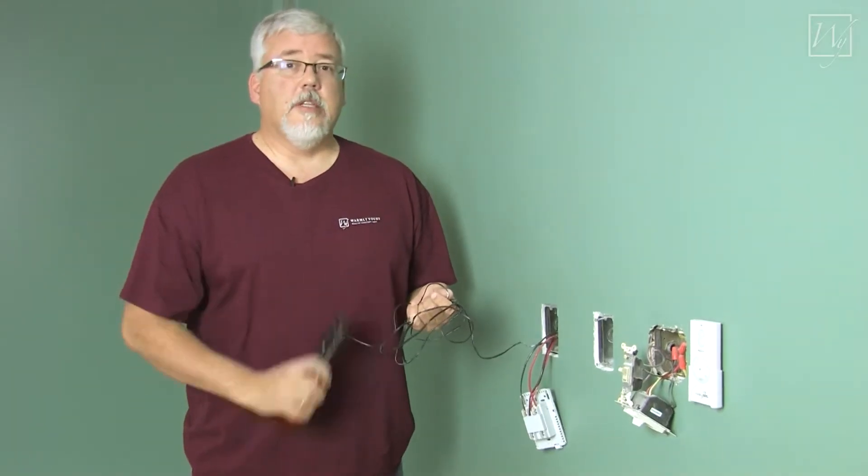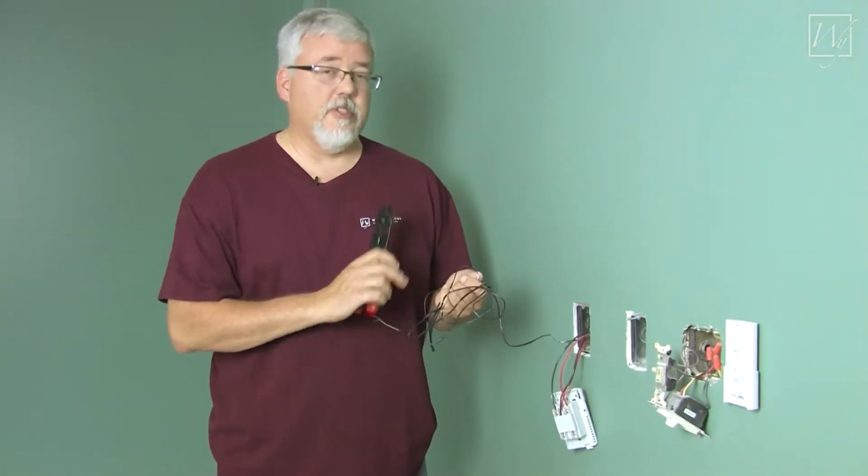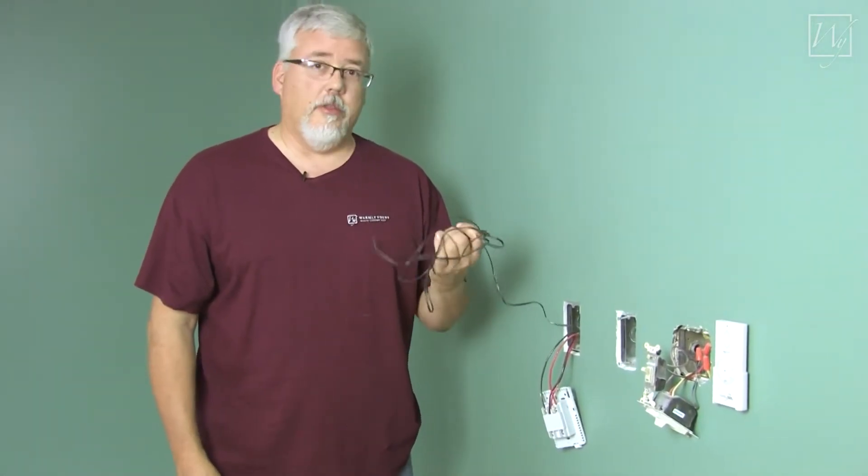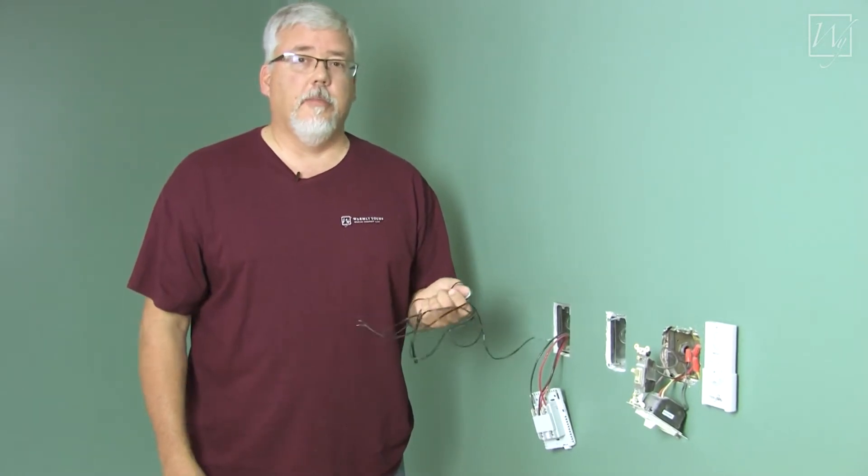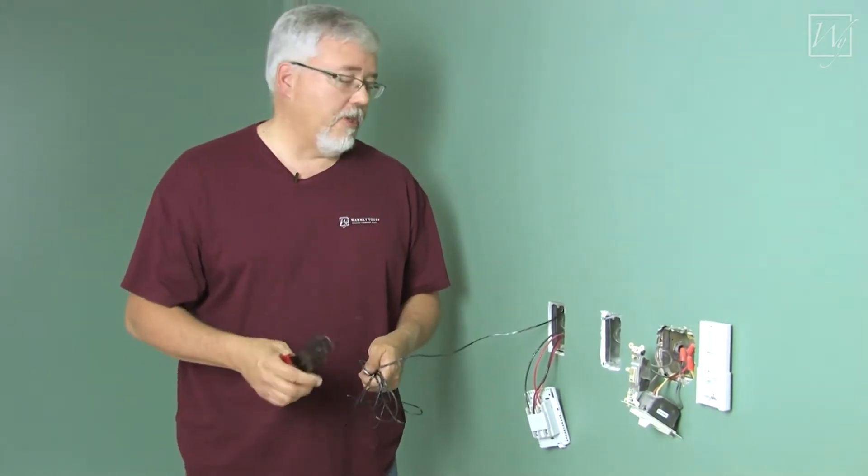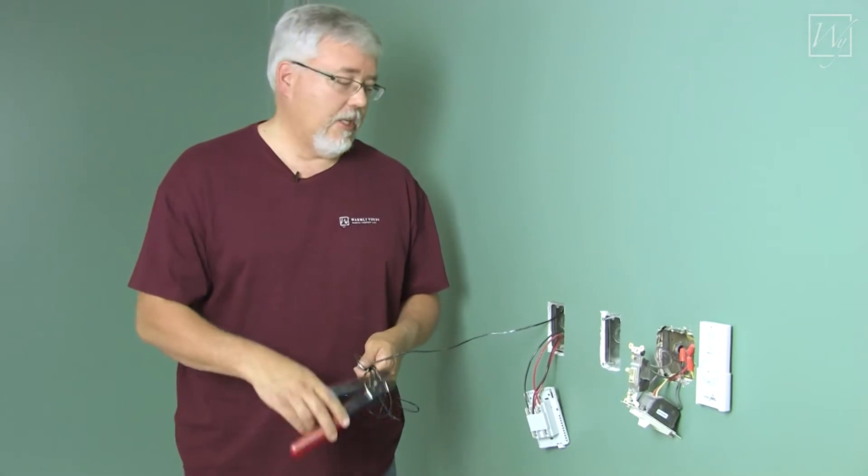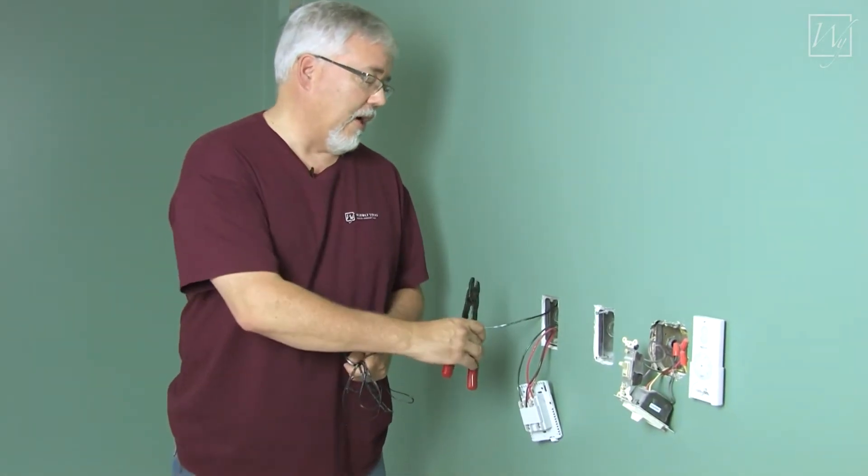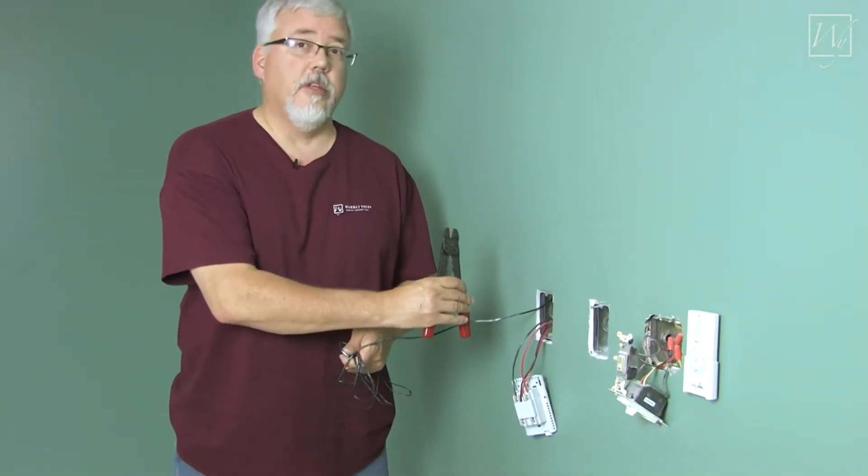Now that we know the thermostat sensor is good, it's time to trim some of this length. You do not need all of this wire, and there's no need to stuff it down into the box. The local code here says you must have eight inches of cable sticking out. So our eight inch mark is about right here, so I'm going to trim it to this spot.